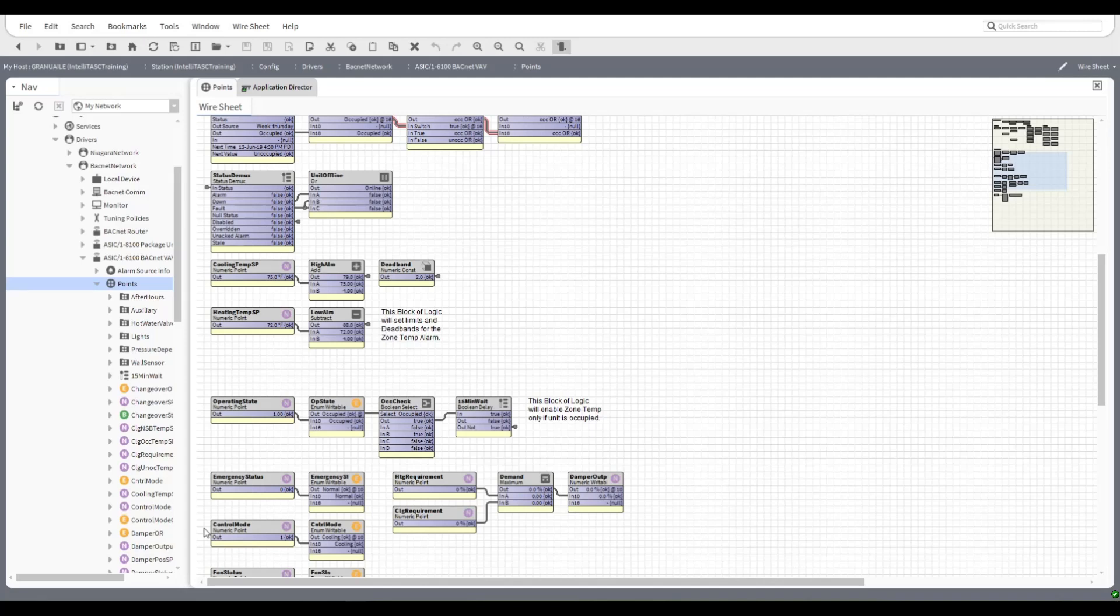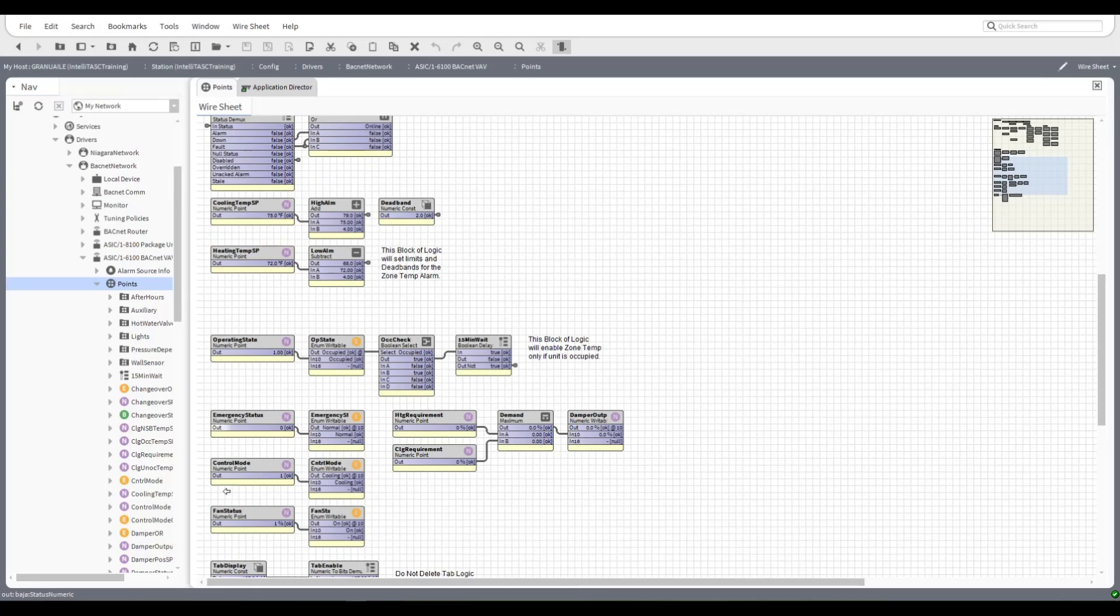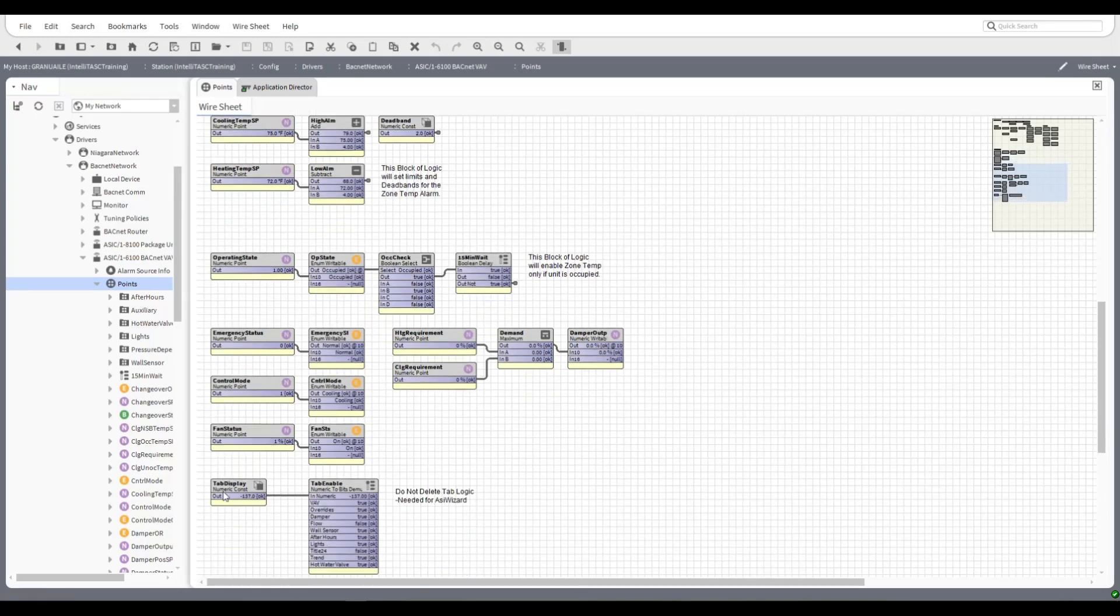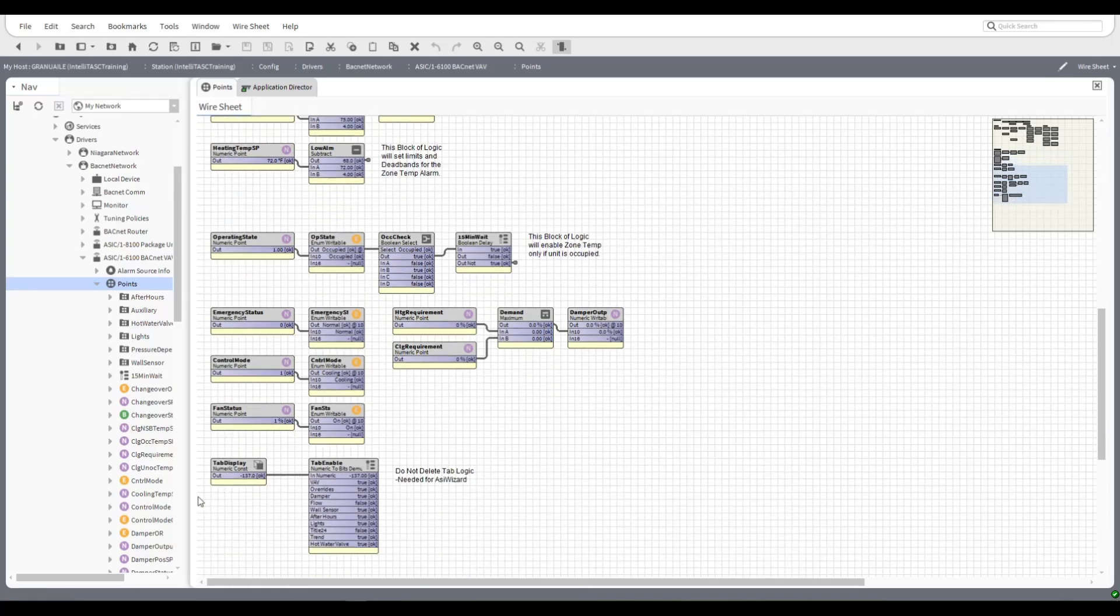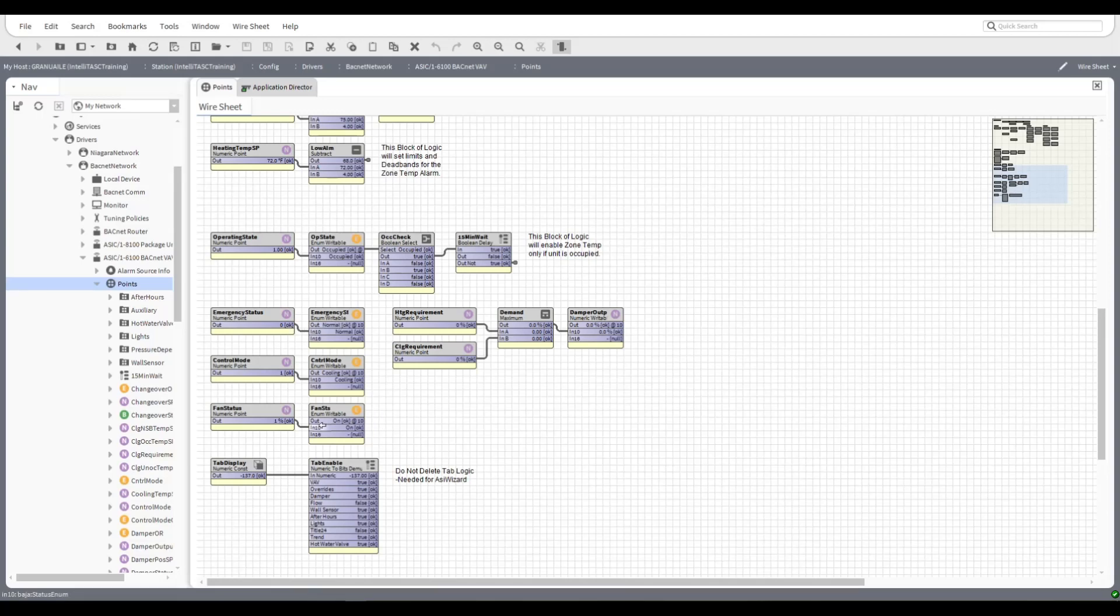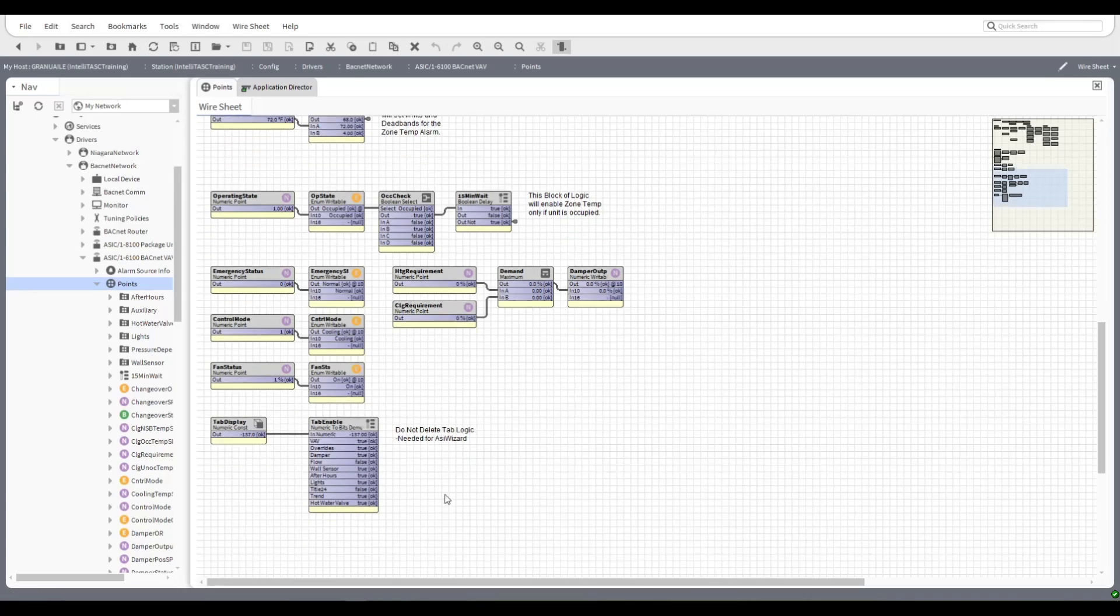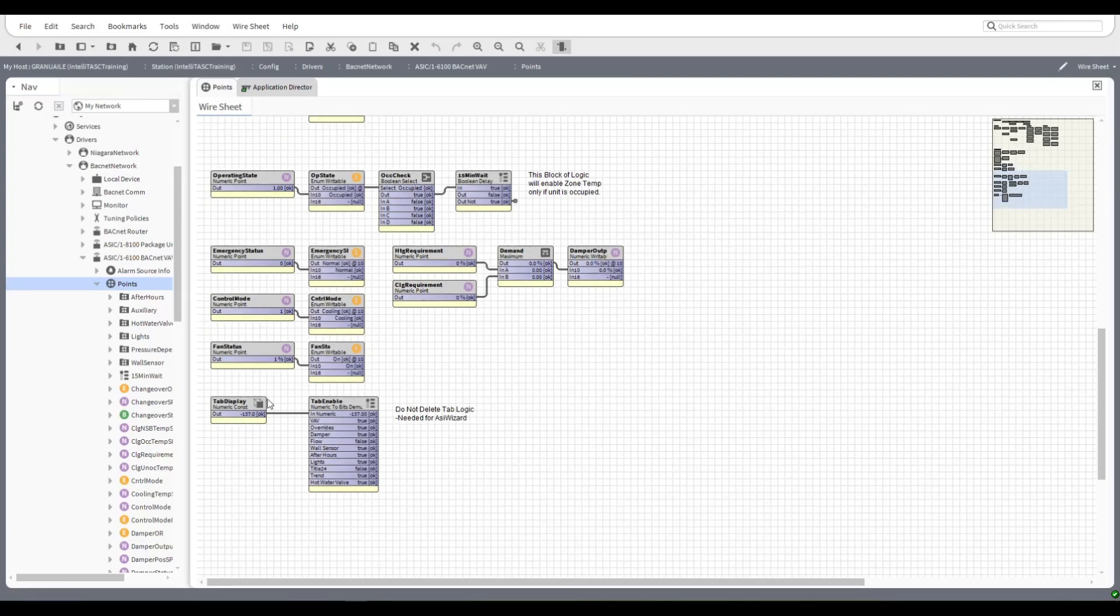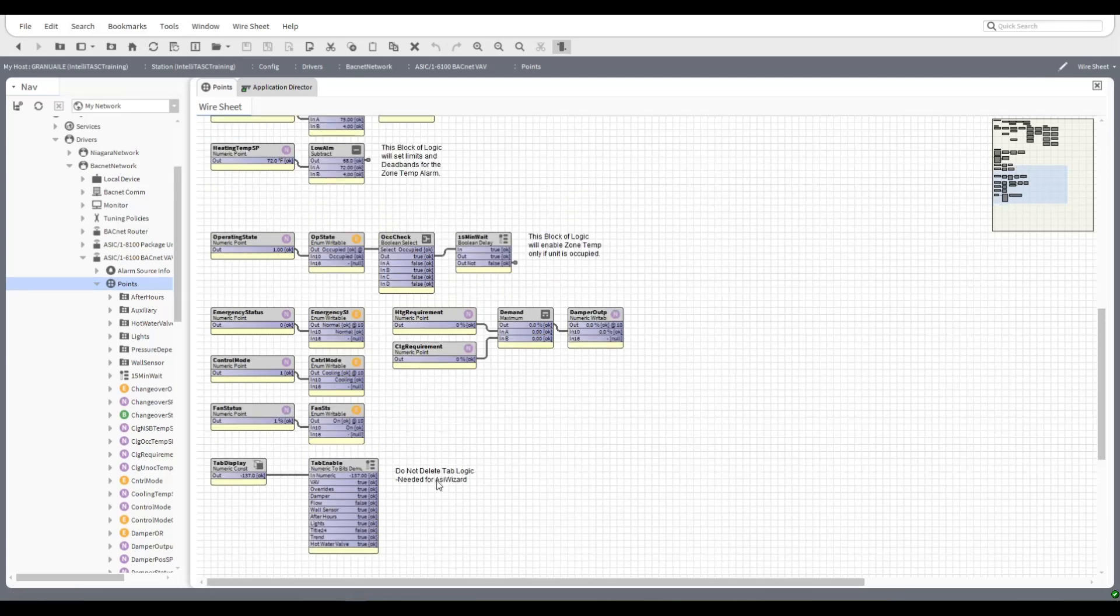Additional to that we have a few other things in terms of checking modes, bringing into enumeration because what we get from the unit is all analog so we turn those into enumerated modes so that's more useful to you. We have this tiny piece of logic at the bottom which will help us control our tabs. If you do modify anything in these wire sheets do not delete this piece of logic over here, the tab display and tab enable. It is required for the px graphics to work.